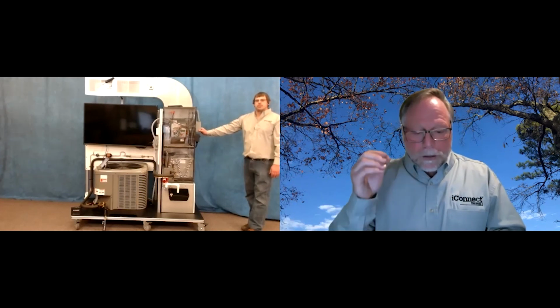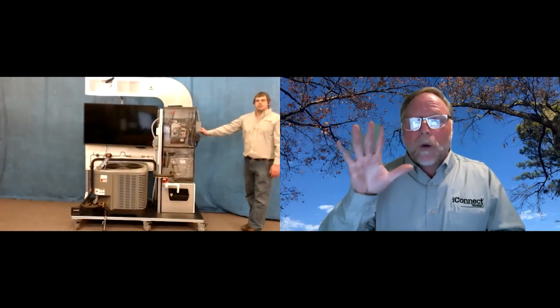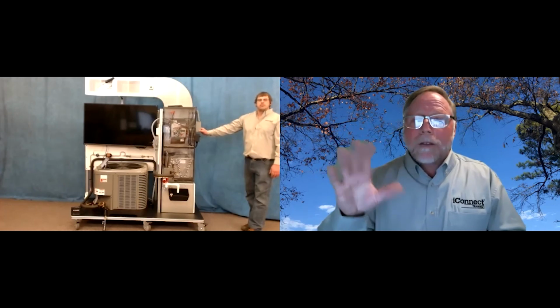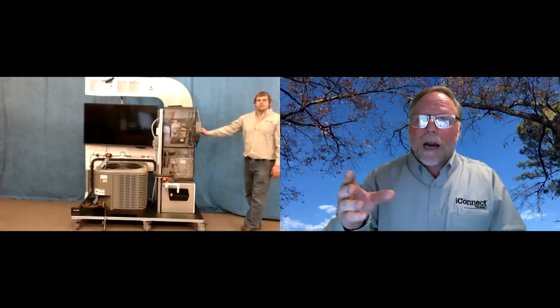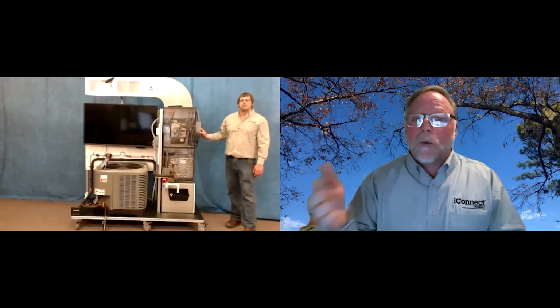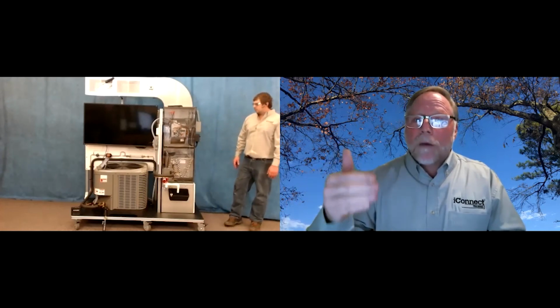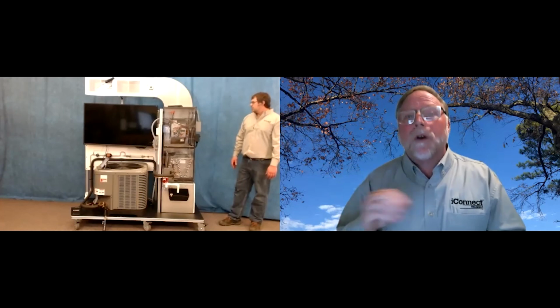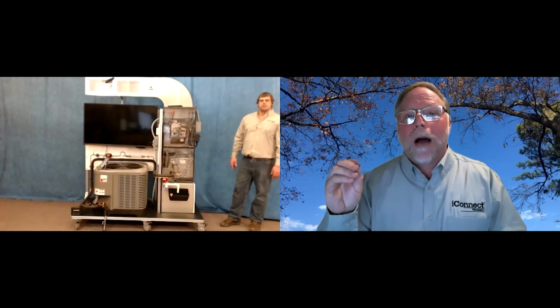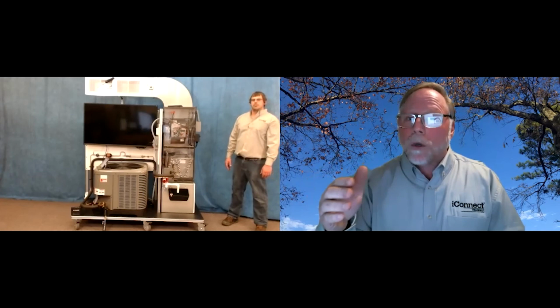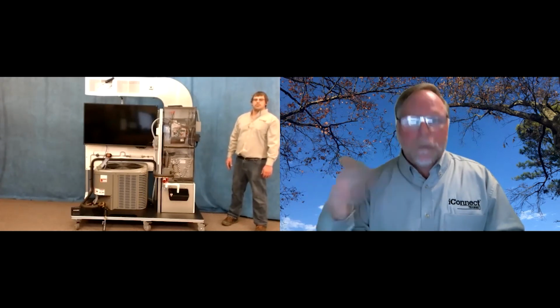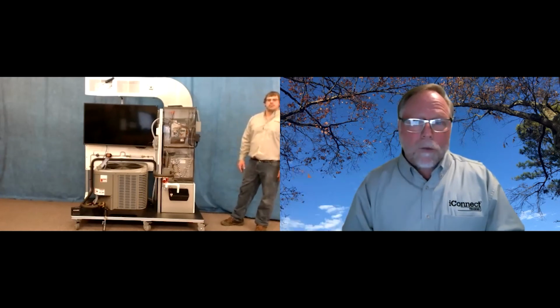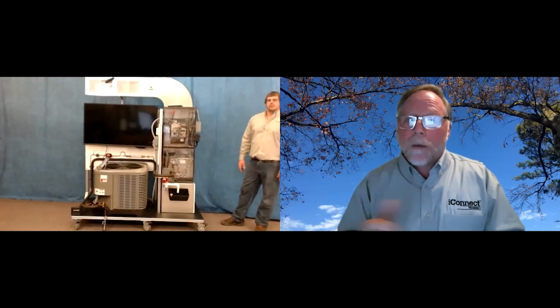The other thing was number 5, which is measuring the wet bulb and dry bulb on the return and the supply, showing how that's affected by airflow, explaining what sensible heat is, what latent heat is, and seeing what dry bulb and wet bulb is. A lot of people have no idea the importance of measuring wet bulb. And this trainer will show how very important that is in removing moisture, which is the number 1 load on the air conditioner, is removing the humidity. And then we can drop the temperature. And we can show that with lesson number 5, measure the wet bulb and dry bulb.